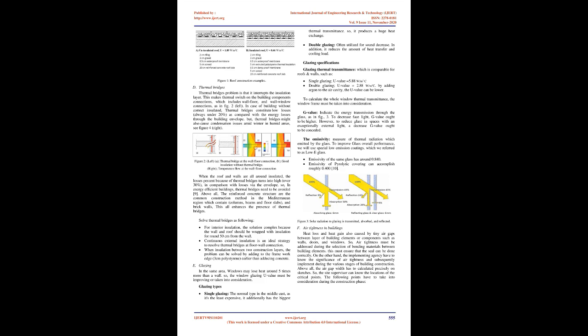C. Roof construction. The roof of the building receives most of the sun's rays per square meter. In this way, it's important that the rooftop has a high thermal capacity and thermal insulation. Like the wall, the U value is the thermal transmittance indicator for the roof. Figure 1 shows two different rooftop constructions. One is insulated and the other isn't. By evaluating the thermal transmittance of those rooftops, we see that the insulated roof has a much lower thermal transmittance and accordingly a higher thermal resistance. So, rooftop insulation is most favored for all climates.